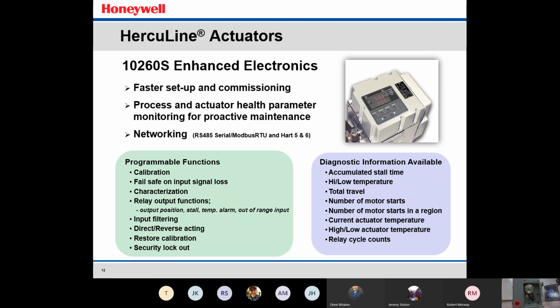Total travel time, so it has an accumulator that pretty much tallies up the total travel time of the actuator throughout the work week, the month, or the year. It also shows you the number of motor starts in a period of time, the current actuator temperature, the high and low actuator temperature that we talked about, and then relay cycle counts. So if you have a high and low switch that is hooked up to the actuator, this can actually count the cycles of how many times it went to high fire and low fire.